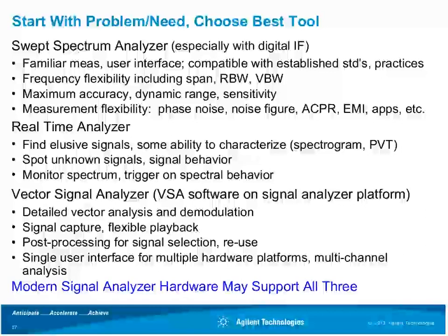And that is, it's an entirely reasonable thing to begin with a swept spectrum analyzer. They have the maximum flexibility in terms of frequency span, resolution bandwidth, and so on. They offer coverage of arbitrarily wide frequency spans. They have a familiar user interface, familiar displays. They're an excellent way to understand what's going on in most systems.